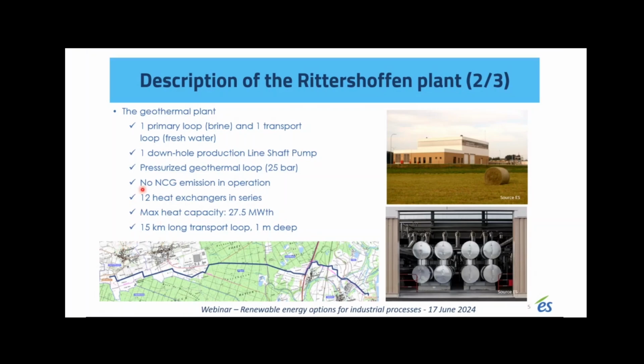The geothermal loop is designed with a downhole production pump. This pump is designed to increase the production flow rate, but also to pressurize the geothermal brine up to 25 bar, in order to keep all the non-condensable gas dissolved in it. So in operation, this geothermal plant has no non-condensable gas emission, meaning no CO2 emission during operation.